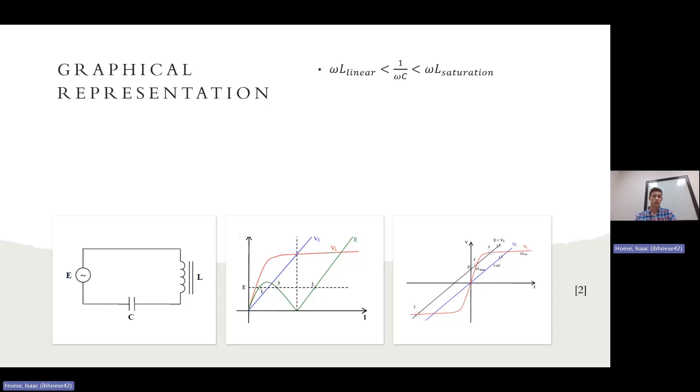And when a phase goes out, we'll talk about that in just a few seconds. The saturation region is entered. So the transformer, obviously the inductance changes into the saturation region. And this could cause an almost instant change from operating point one to two. And this is where the multiple solutions come in because you don't know what inductance that's going to happen at.